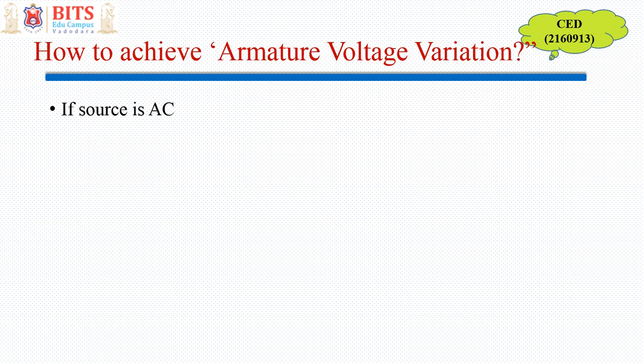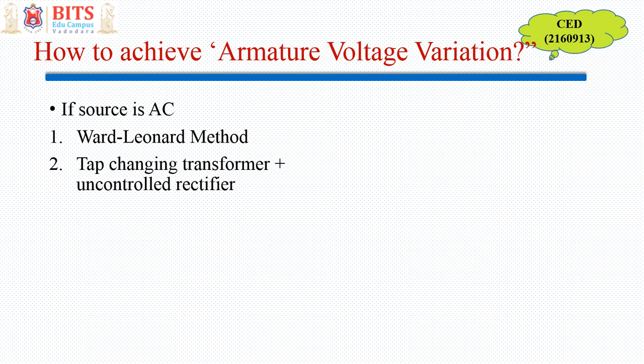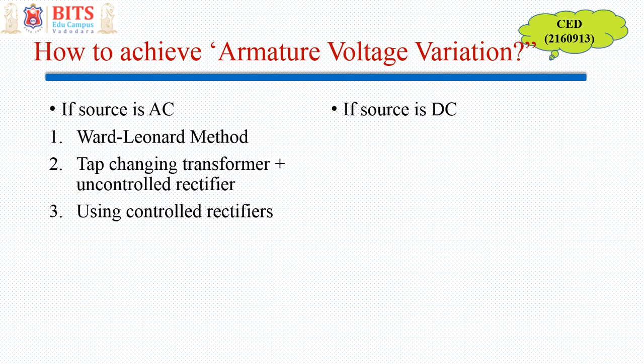The classification of different methods depends on the source. If the available supply for the motor is AC, then we have the following methods: one is the very old method known as the Ward-Leonard method; second is a very old method used in old locomotives — tap changing transformers with uncontrolled or diode rectifier; and third is the latest popular method using controlled rectifiers with SCRs, where we can control using the firing angle.